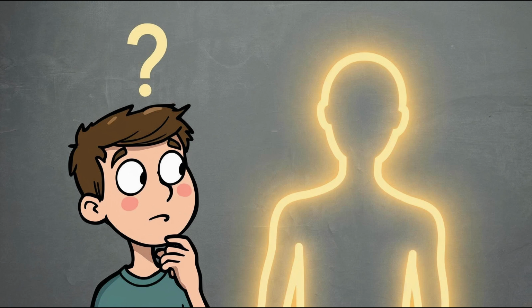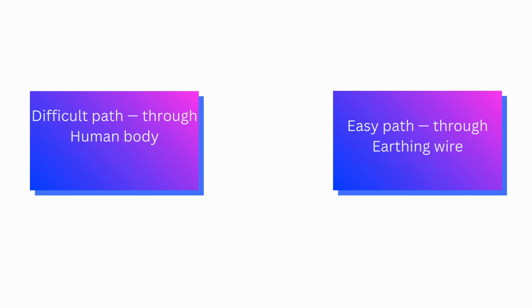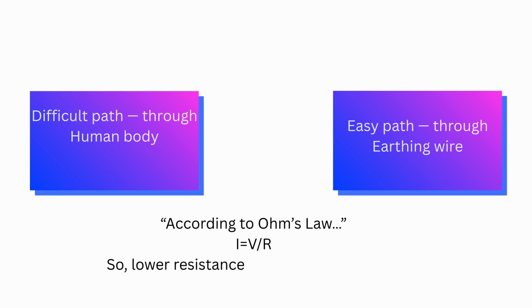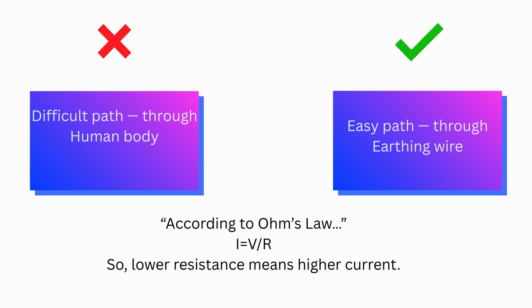Now compare this with a human body. Human body resistance can range from about 1 lakh ohms when dry to around 1000 ohms when wet, while earthing resistance is usually below 5 ohms, and in good systems even less than 1 ohm. So electricity has two choices: a difficult path through your body, and an easy path through the earthing wire. According to Ohm's law, current I equals V divided by R, so lower resistance means higher current. So almost all current flows through the earthing wire. Technically, current flows through all available paths, but because earthing resistance is so low, more than 99% of the current flows through it, and only a negligible amount may pass through your body.